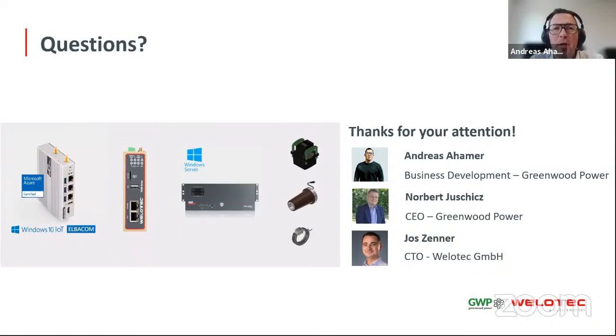Thanks for that. Next one for Norbert. Is there any use case of Greenwood power sensors in metered ring main units? Yeah, we speak about revenue measurement. We speak about current sensors class 0.2S, 0.5S, which are necessary to make some kind of metering or revenue measurement. Yes, we can provide such kind of products. There is only one challenge. There is in Europe, as far as I know, no official institute which could confirm this high accuracy class at the moment. This is the major problem at the moment.